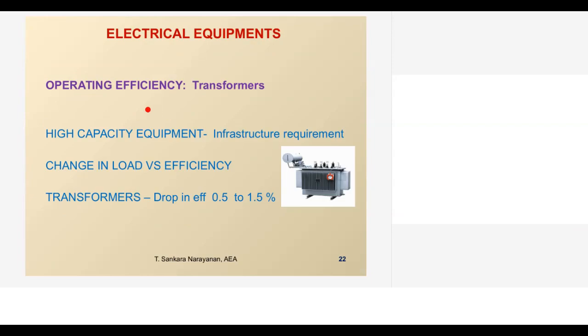So for a transformer, how much percentage can the operating efficiency drop? Because a transformer is capital-intensive equipment, it is done during the infrastructure stage. So suddenly, if the audit finds certain losses, I may not get an opportunity to replace the transformer. But distribution companies, instead of reducing the load, can reduce the loss in the transformer.